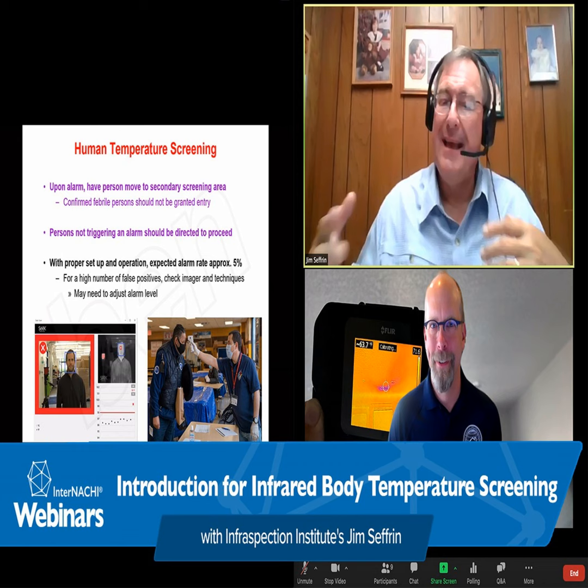Be aware that all thermal imagers are subject to measurement uncertainty. These are often referred to as accuracy specifications. A typical value is within plus or minus 2 Celsius degrees, or 3.6 Fahrenheit degrees. Systems that have integrated black bodies, these are dedicated, very expensive systems ranging anywhere from around $8,000 and up, although there are some cheaper than that, are typically within 0.3 C degrees. They're designed to be highly stable and accurate. In order to understand more about measurement uncertainty, consult the manufacturer's literature for further information.